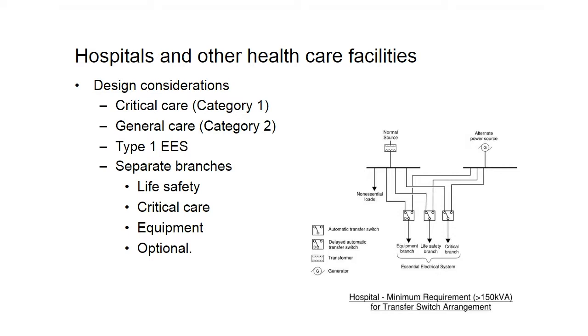So there's many considerations to be taken into account when designing the emergency electrical system. These include, and are not limited by, the things that I've indicated on the slide here. So starting with critical versus general care occupancy or room types, the critical care is category 1 versus category 2 in the general care. And really the difference here is the level of risk that's involved to the patient or the occupant within the space.